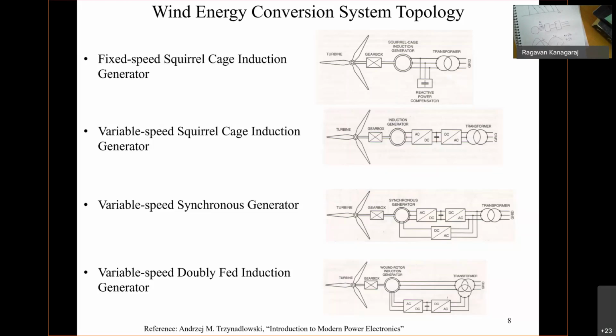So when I say there is a converter giving power to the grid, don't think that active power is simply taken from the generator and goes to the grid. To get that active power, you require a magnetic field. That magnetic field is established by the grid supply, for which you will have to do appropriate control on these converters.